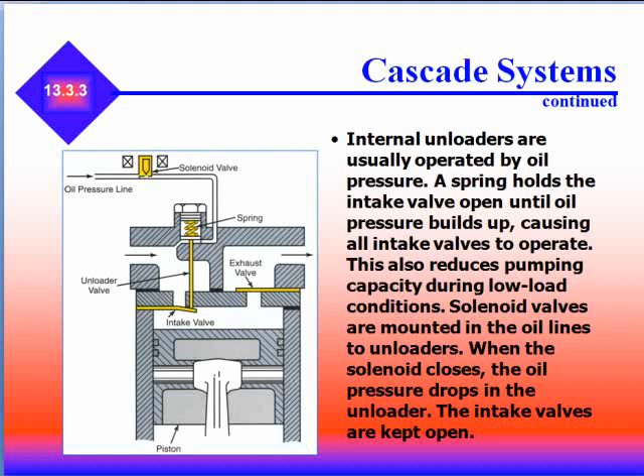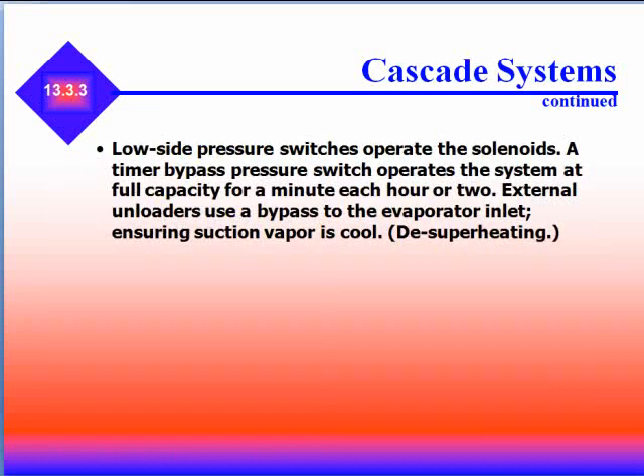When the solenoid closes, the oil pressure drops in the unloader and the intake valves are kept open. Low side pressure switches operate the solenoids. A timer bypass switch operates the system at full capacity for a minute each hour or two. External unloaders use a bypass to the evaporator inlet, ensuring suction vapor is cool — in other words, de-superheating it.